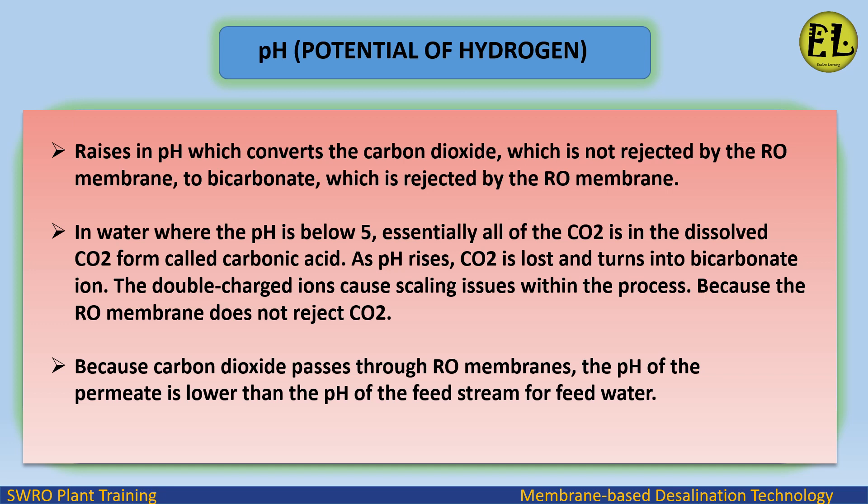Because the RO membrane does not reject CO2, and carbon dioxide passes through RO membranes, the pH of the permeate is lower than the pH of the feed stream.